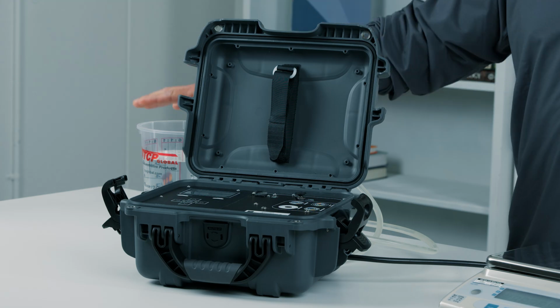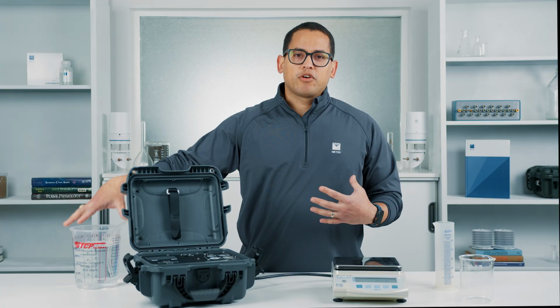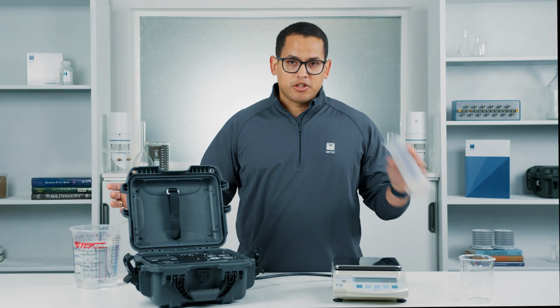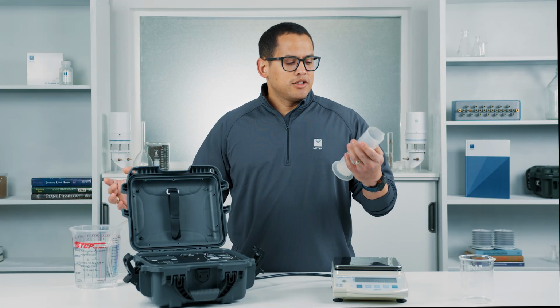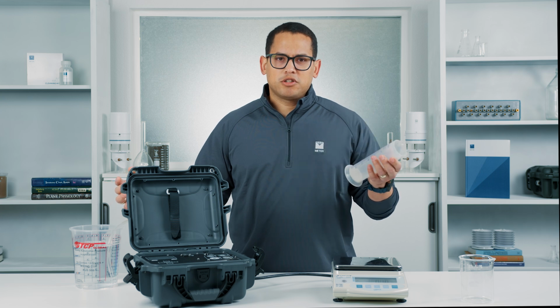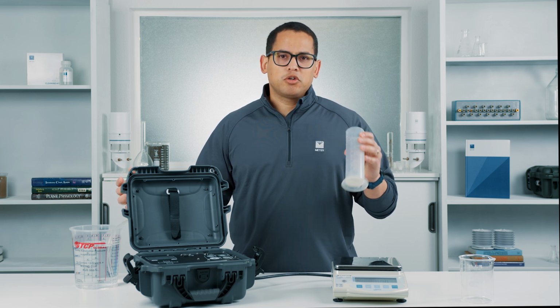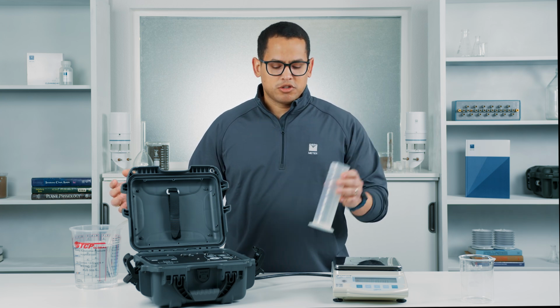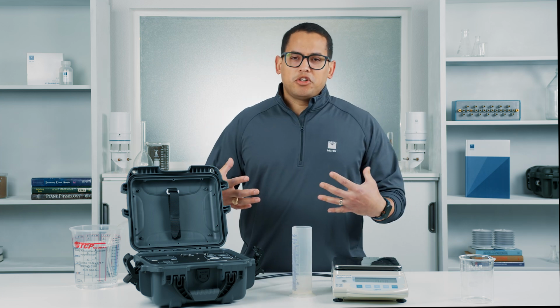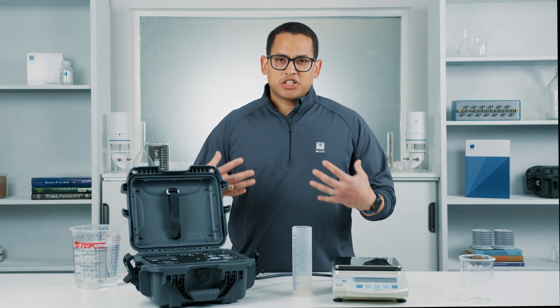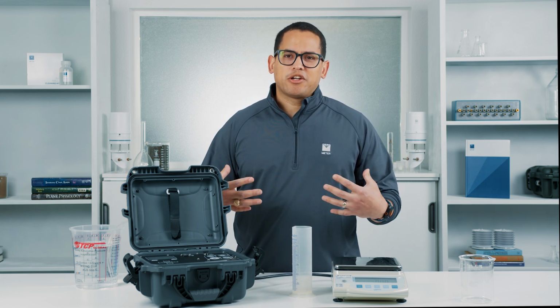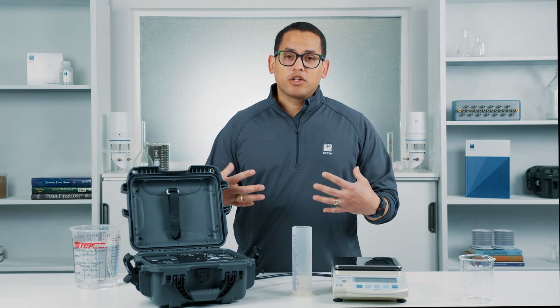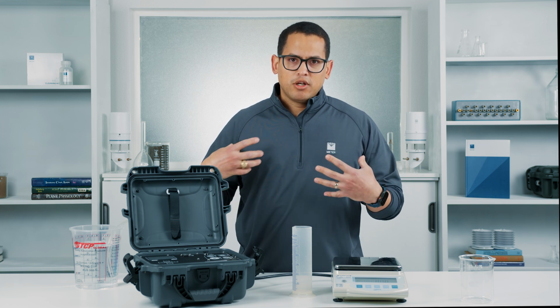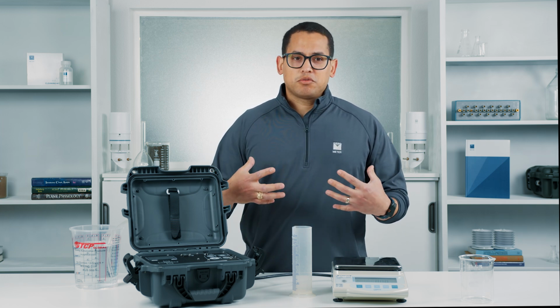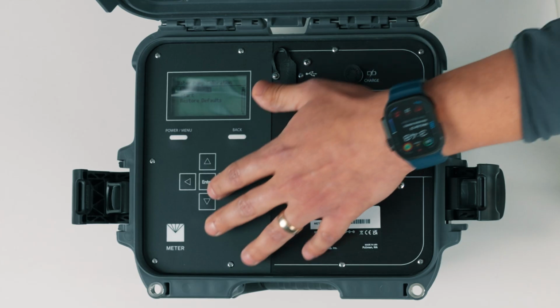So before we start our calibration, we're going to want to make sure we have our water supply feeding water from the reservoir. And we're also going to need to grab our graduated cylinder. This is a 250 milliliter graduated cylinder. This is a little big. You could go down to a 100 milliliter graduated cylinder as well if you wanted. The first thing we're going to do to start the calibration process is actually purge the lines to get any air out of the lines. That way we're only running water through the line during the calibration process. So to do that, the first thing we're going to do is go ahead and go down to the start button.